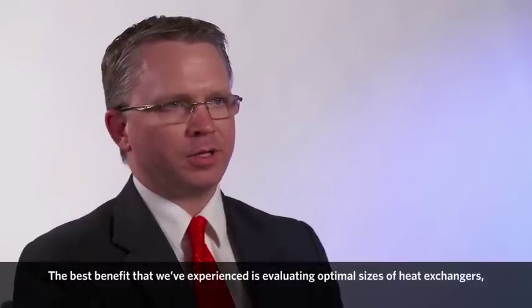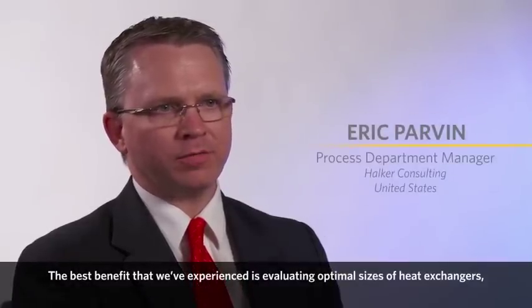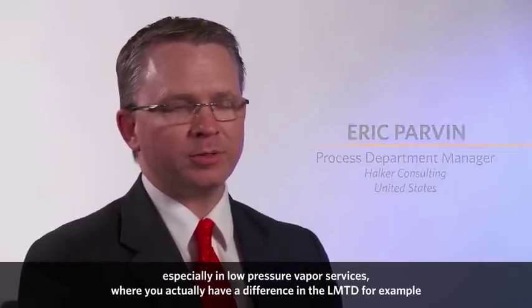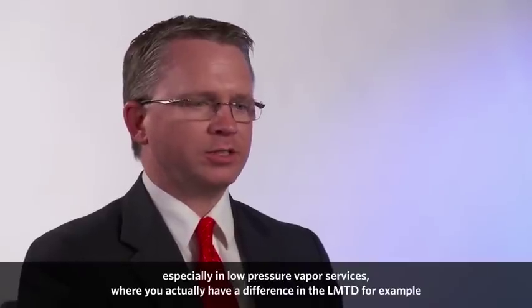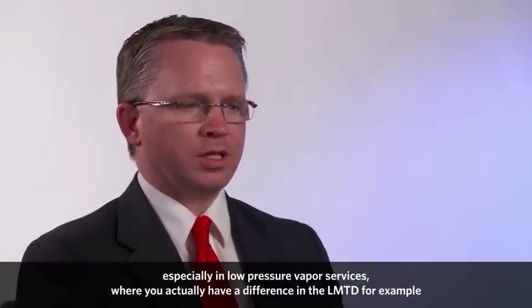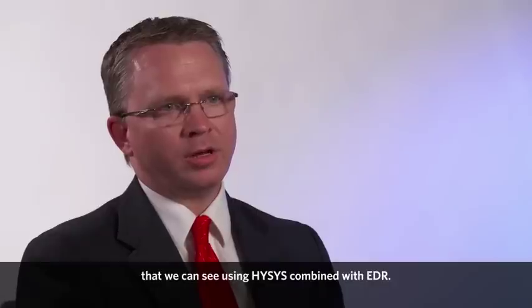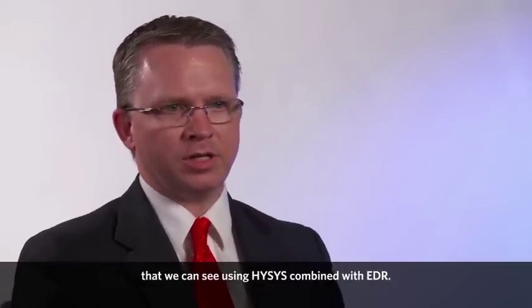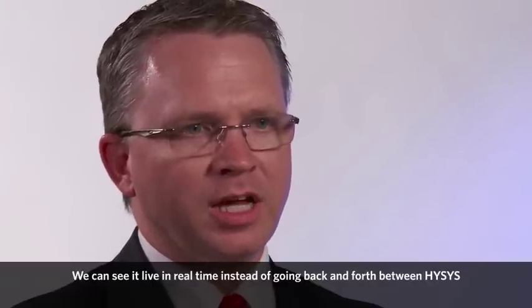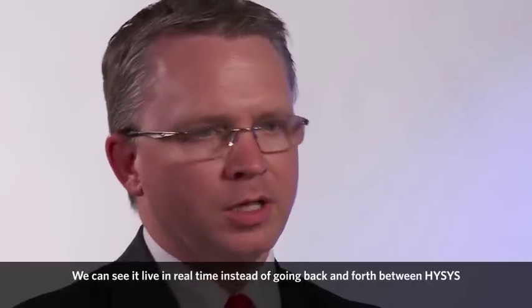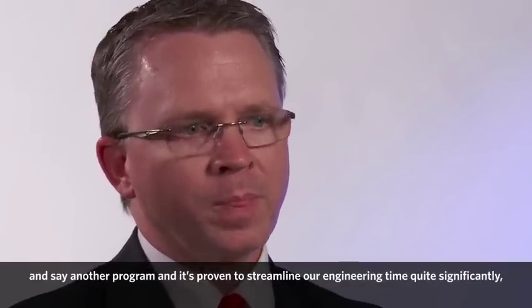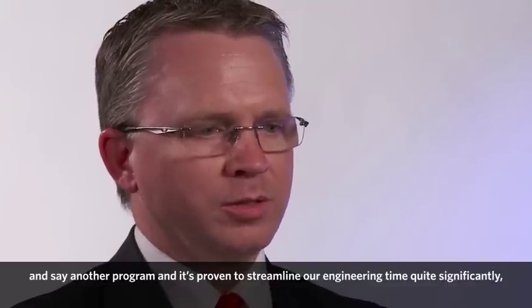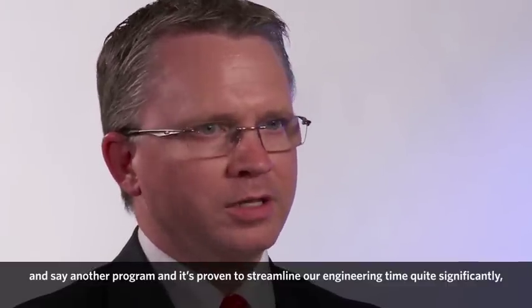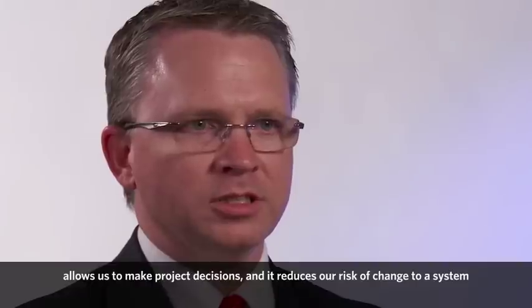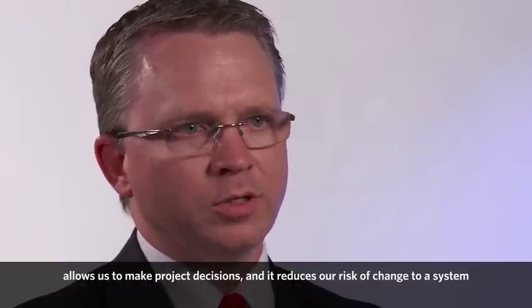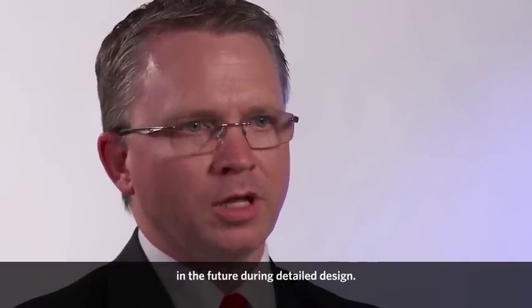The best benefit we've experienced is evaluating optimal sizes of heat exchangers, especially in low pressure vapor services, where you actually have a difference in the LMTD, for example, that we can see using HYSYS combined with EDR. We can see it live in real time instead of going back and forth between HYSYS and another program. It's proven to streamline our engineering time significantly, allows us to make project decisions, and reduces our risk of change to a system in the future during detailed design.